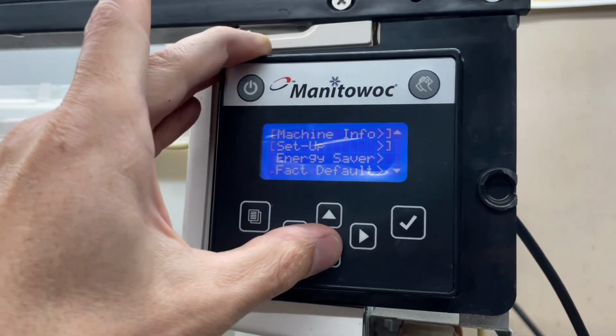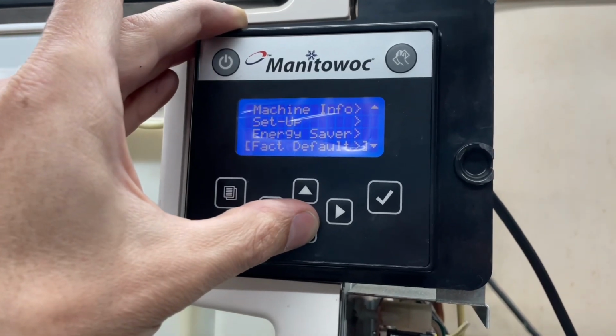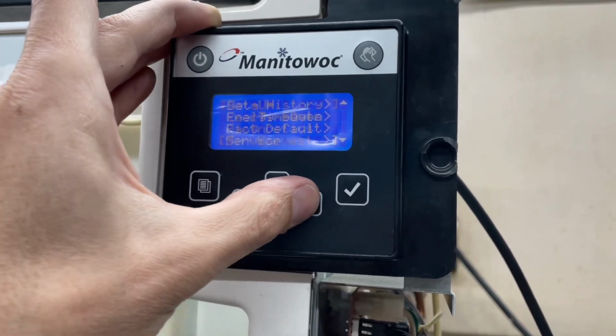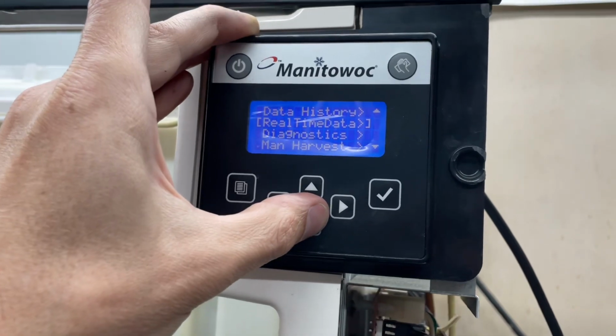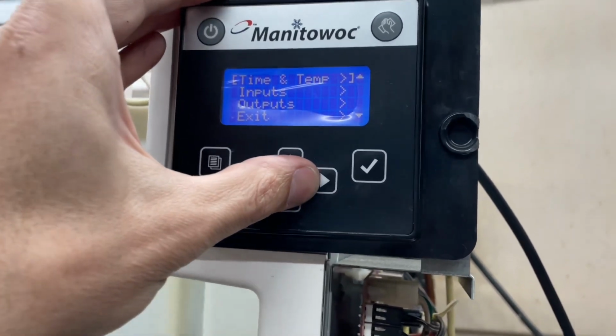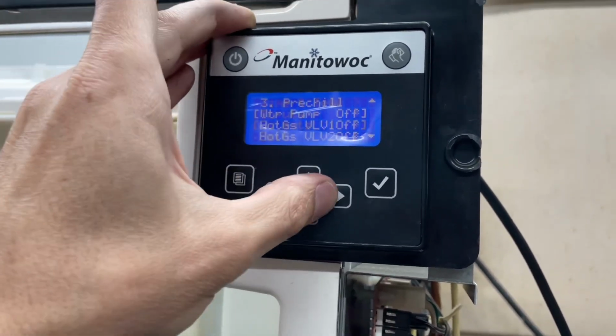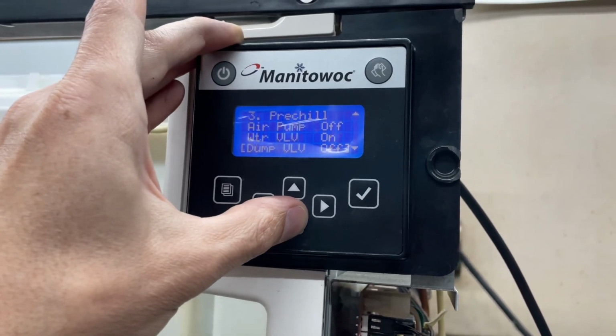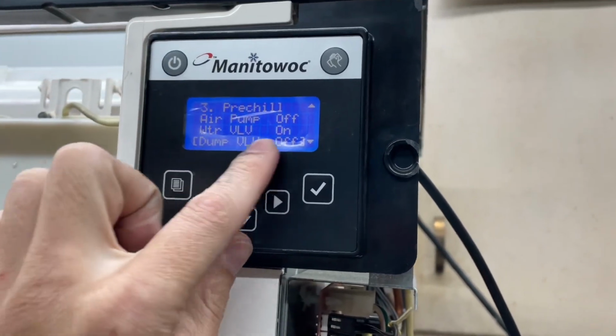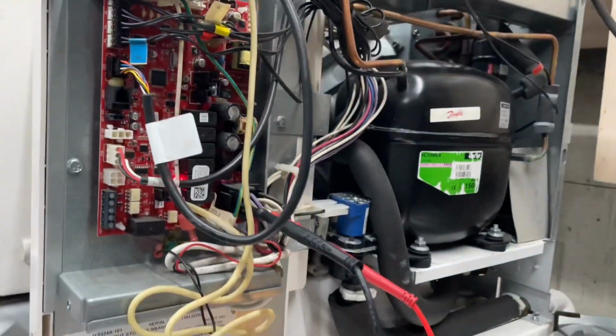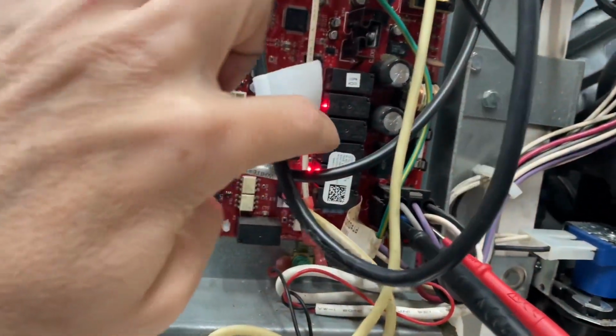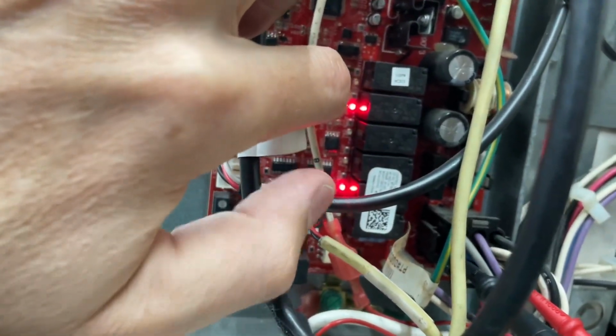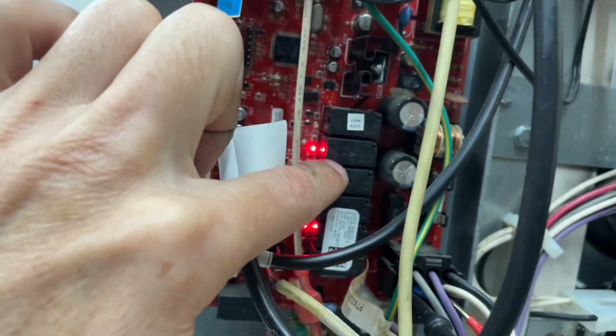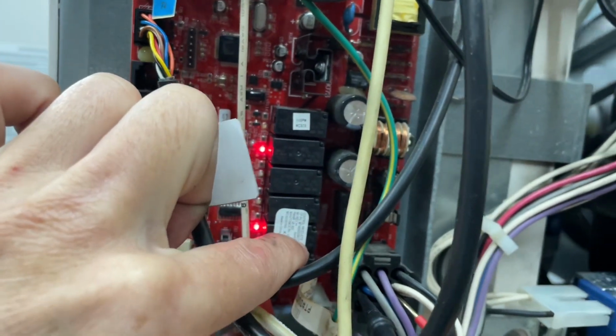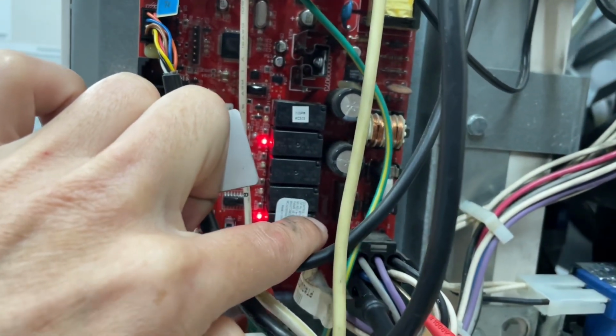All right, we made it through the purge. We're in pre-chill now. We should be filling up with water, but we're not. We're gonna go to our display. We're gonna go down to our water valve. This tells us water valve should be on. You can also see that here at the board. One of these relays is labeled water. It's number 2 down there, or 1, 2, 3, 4, 5, depends on which way you count. It's labeled water right back down in there.